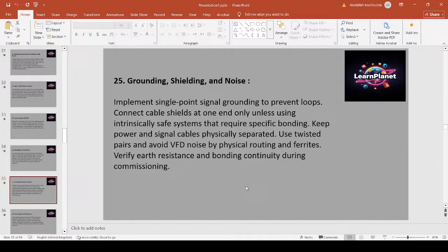Grounding, shielding, and noise. Implement single point signal grounding to prevent loops. Connect cable shields at one end only unless using an intrinsically safe system that requires specific bonding. Keep power and signal cables physically separated. Use twisted pairs and avoid VFD noise by physical routing and ferrites. Verify earth resistance and bonding continuity during commissioning.